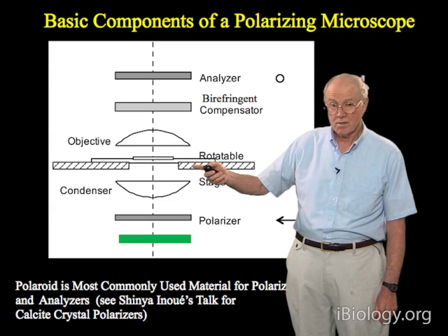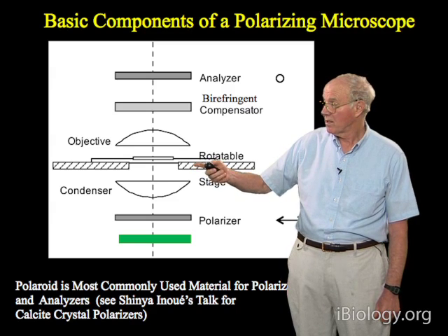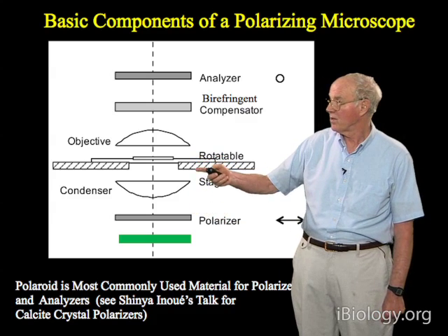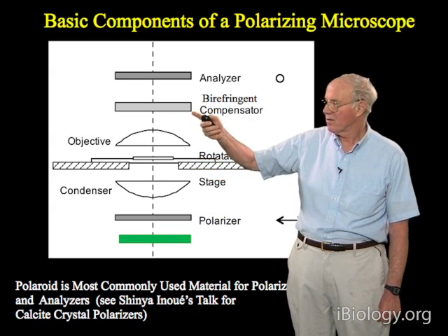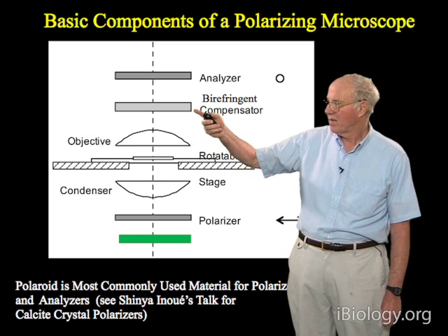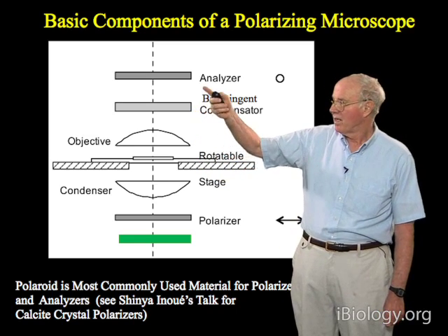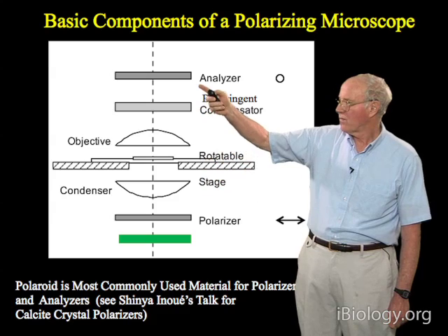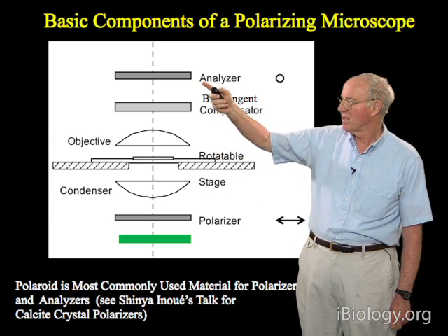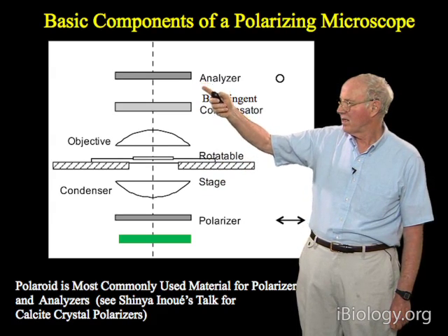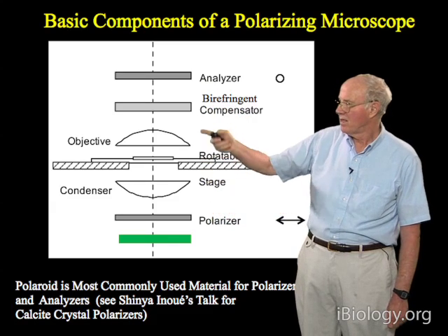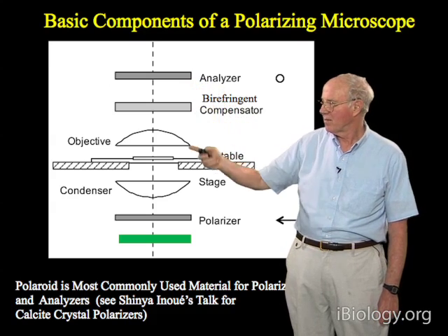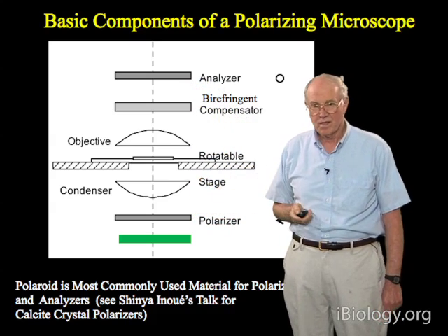Contrast is dependent on the rotation of the specimen relative to the polarizer's transmission azimuth. Polarizing microscopes can also have birefringent compensators. In addition, there is an analyzer — a polarizer whose vibration transmission direction is oriented at 90 degrees to that of the polarizer — so it's at the extinction position, canceling the light coming from the polarizer in the background.